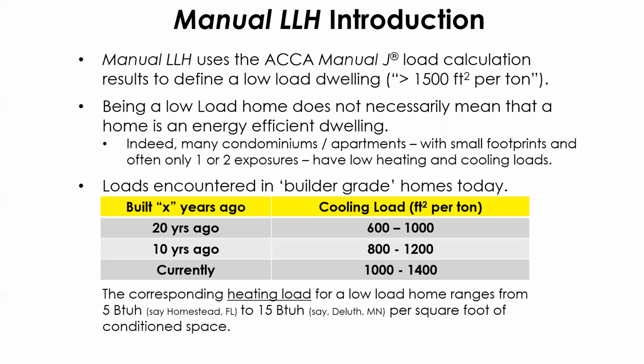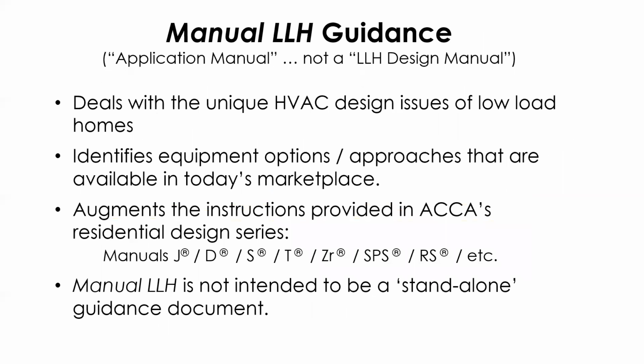For those of us in the heating market, especially for someone like me in Michigan, we probably care more about heating than cooling. So a low-load home might be a 5 BTU per hour per square foot home in Homestead, Florida, up to 15 BTUs per square foot in Duluth, Minnesota. Manual LLH is actually an application manual and not a design manual like you're probably used to. It deals with the unique HVAC design issues of low-load homes, identifies some equipment options and approaches that are available in today's market, and augments the instructions provided in the existing manuals. It's not intended to be a standalone document. So you can't just buy Manual LLH and not have to buy J, D and S, because it will not work that way.